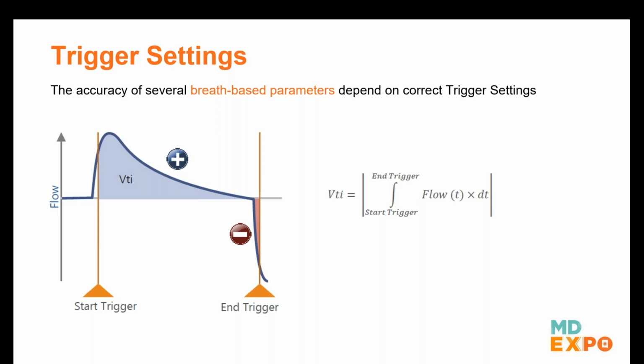In this example, you can see our triggers are a little bit too late. The inspiratory phase starts here, but our trigger is a little bit shifted. The same applies for the end trigger here. It's also a bit delayed. What happens here is we're going to miss in the calculation this first part of the volume. But even worse, it's going to take a bit of the exhalation phase and also consider this as inspiration tidal volume. And because the flow in this example goes negative here, this is going to be considered negative, so it's going to be deducted from the calculated volume. So in examples like this, we will have a tidal volume which is not really accurate anymore because our trigger settings are not accurate.